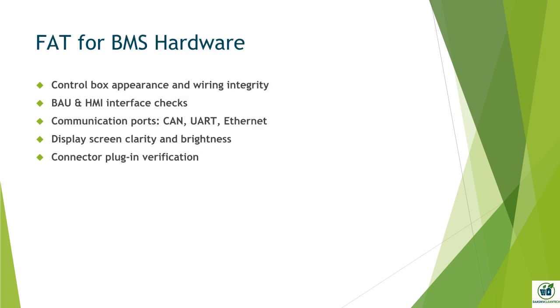The BMS hardware is inspected for build quality and wiring integrity. The control box must be free of corrosion and physical damage. BAU and HMI interfaces are tested for responsiveness and data accuracy. Communication ports, including CAN, UART, and Ethernet, are verified for reliable data exchange. The display screen is checked for brightness, clarity, and correct labeling.